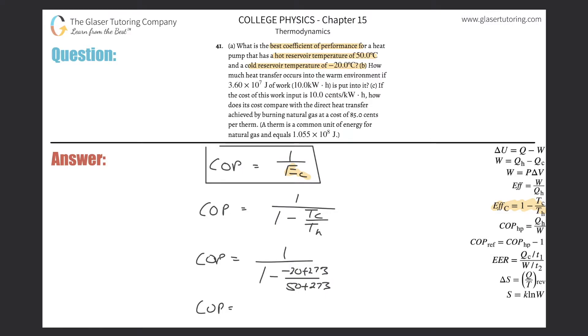Simply plug it into the calculator. So I'm going to do the denominator portion. So negative 20 plus the 273 divided by 50 plus the 273, and then one minus that value. The denominator is about 0.2. And then when you do the math, one divided by that, it works out to be about 4.61. So 4.61, that's the best possible coefficient of performance. All right, so that takes care of letter A.